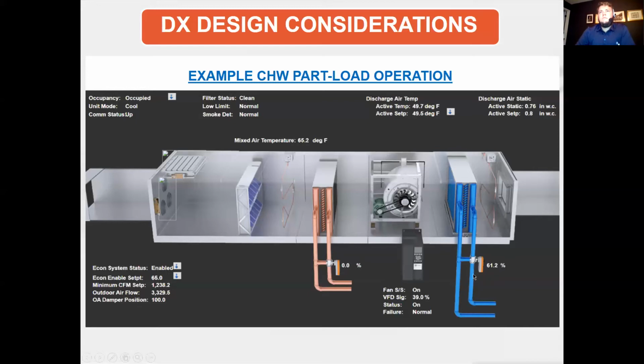So this shows you the things that you can do. If this was an air-cooled condensing unit, this would be like the worst day possible for a DX system because the load is low. As we talked about, the condensing unit actually has more capacity on a 65-degree day than it does on a 95-degree day. So it's going to be struggling to try to maintain that 50-degree leaving air temperature for us. Yeah, so as we talked about, we're asking these really large DX systems to do a lot on the really big applications when we're applying things like VAV airflow control, part load, economizer. If you compare that against something like this, where the chilled water valve simply modulates, 61% at a constant temperature, 39% VAV, it just inherently can handle it maybe a little better in some applications, right? So it's something we wanted to bring awareness to.